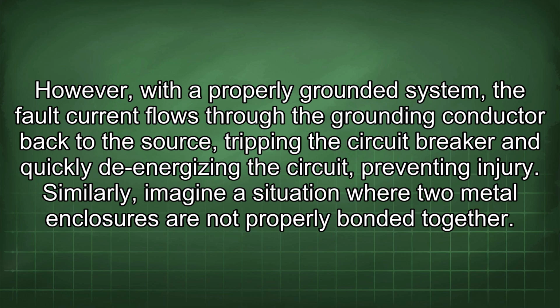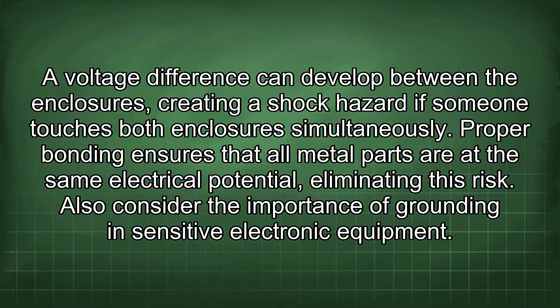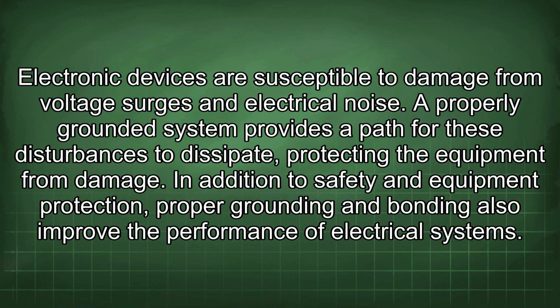Similarly, imagine a situation where two metal enclosures are not properly bonded together. A voltage difference can develop between the enclosures, creating a shock hazard if someone touches both enclosures simultaneously. Proper bonding ensures that all metal parts are at the same electrical potential, eliminating this risk. Also consider the importance of grounding in sensitive electronic equipment. Electronic devices are susceptible to damage from voltage surges and electrical noise. A properly grounded system provides a path for these disturbances to dissipate, protecting the equipment from damage.